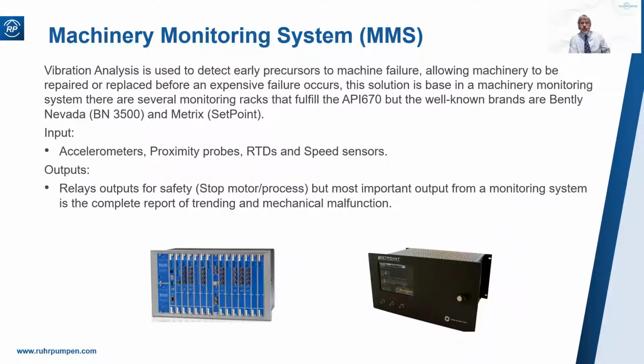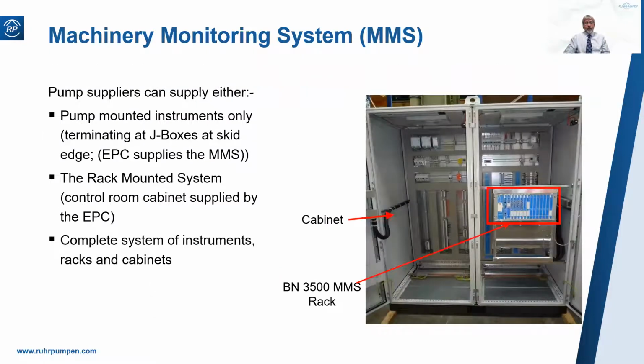Machinery monitoring systems, usually installed in the remote control room, take the signals from accelerometers, proximity probes, RTDs, and speed sensors, and process them to give analytical reports for trending, scheduling maintenance, and predicting failures. Commonly supplied by Bently Nevada and Metrix, big names in this one. Now, they can be supplied by the pump vendor, or more commonly, they'll be supplied by the EPC.